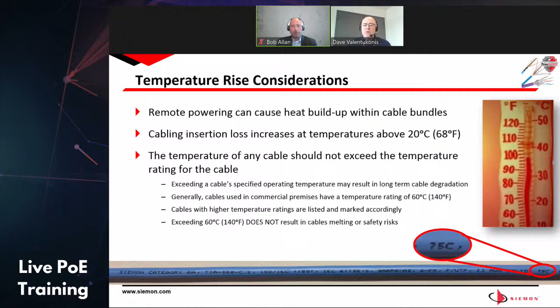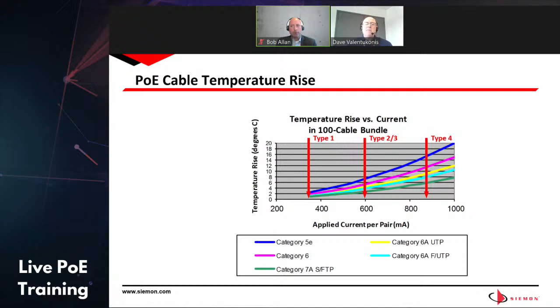Depending on the amount of current you apply, whether it's type 1, which is 15 watts, type 2 or 3, which is 30 and 60 watts, or type 4, which gets closer to 90 watts, you have a temperature rise in the cable bundles, and it changes depending on the category of cabling. Category 5E, for example, is less tolerant of it because it has smaller conductors. As you go up the ladder to category 6, category 6A, category 6A shielded, and even category 7A, which is a fully shielded system, the cabling can manage heat dissipation better over the length of the run. So ultimately you have to apply a certain level of derating if you're addressing temperatures up to 60 degrees.